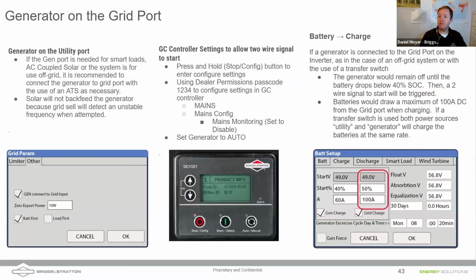Yeah, so our generators are grid sensing. So they're looking for grid, and if grid goes away, they're going to start up. The grid flowing to the generator not only is used for grid sensing, but also keeps the starting battery and any battery warmers charged up. So what we need to do is tell the generator that even if it still sees grid, because you're probably going to want to feed that off the backed up loads panel, still start if you see that 2-wire signal to start. Yes, exactly. So we're going to disable the auto main sensing. The instructions are on the screen there.